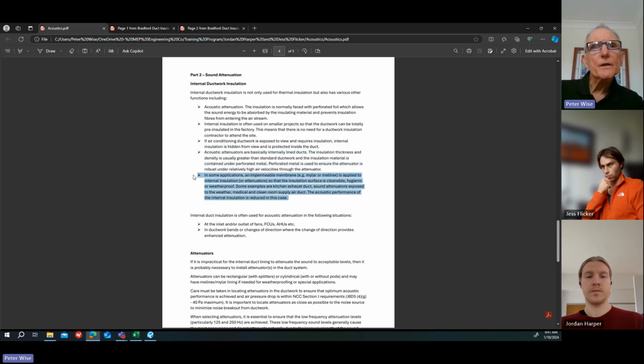In some applications, an impermeable membrane, a couple of ones that are used are Mylar or Melinex, which is like a polythene sheet, is applied to internal insulation or attenuators. So the insulation surface is cleanable or hygienic or weatherproof. Some examples are in kitchen exhaust ductwork. So if you have an attenuator in a kitchen exhaust duct, you would always put this Mylar or Melinex inside. Sound attenuators exposed to the weather, if you've got one outside on a smoke exhaust or something, you'd probably have Melinex. And medical and clean room supply air duct sometimes has that too.